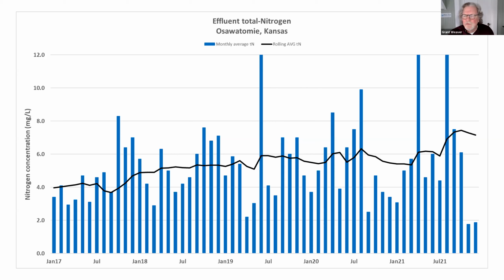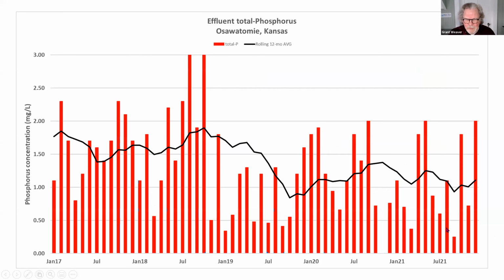because the other examples are very similar. We're seeing periods of great phosphorus removal and then periods of not so great phosphorus removal. While the trend here at Osawatomie has been an improvement because of a greater effort being paid because of recycling the sludge, but still not quite where we want, right, dancing at this 1 milligram per liter, which is the state's long-term goal for all of its treatment plants.